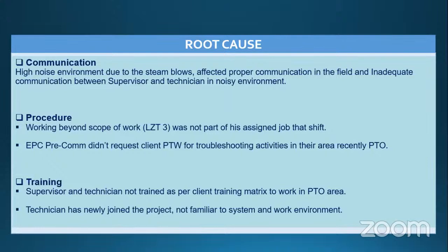Second root cause is the procedures. Two of the boilers and their system had already been PTO'd from project to operation. The technician worked beyond the scope of the job. LZT 3 was not part of his assigned job that shift, since the permit was issued from the EPC side to rectify or troubleshoot LT1 and LT2. But instead, the supervisor avoided working on LT1 and LT2 and started work on LZT 3, a critical level transmitter. This is the first root cause from the procedure.